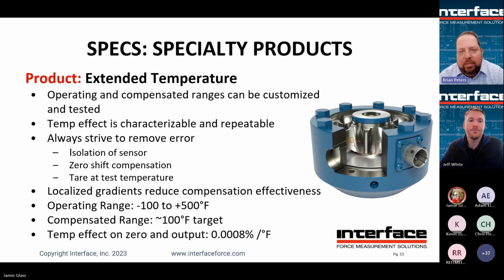In general use, yes, we talked about how we can compensate load cells to different temperature requirements. In actual application, of course, you want to try to keep it away from the temperature if you can, right? Get it out of the thermal chamber or isolate it. Oftentimes it introduces more error if you've got to go through some sort of barrier sleeve or something. So if it is in there, there are things you can do. You can perhaps just test to see how the zero shifts as you sweep through the temperature range for your test without actually applying the load. You can characterize it that way, maybe take it out of your signal.